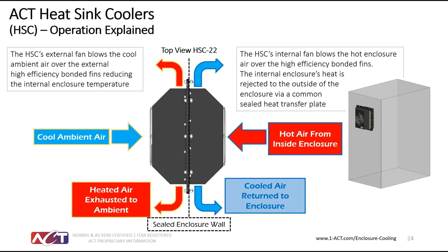And just to give you an overview, top view, so if you look at the top on the right side, you get the air from the internal cabinet. The hot air from the inside of the enclosure comes across the fan, and there are fins that are bonded to the center plate, which is sealed from the outside. So as the fan blows across those fins, it starts to reject the heat to the outside, but because we're rejecting the heat to the outside, that center plate becomes cooler and cooler so that you're cooling the inside of the cabinet, but you're heating the air flowing from the outside fan. But you don't care because it's on the outside. So what we're trying to gain here is the cooling effect of that heat sink or those devices cooling very nicely inside of the unit from the inside. And you're rejecting the heat to the outside.